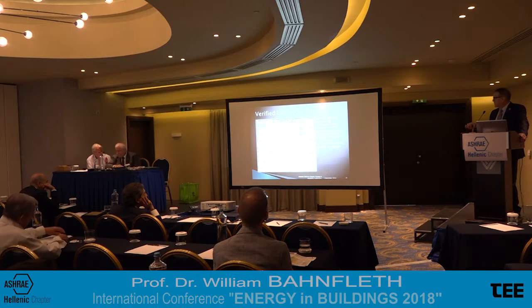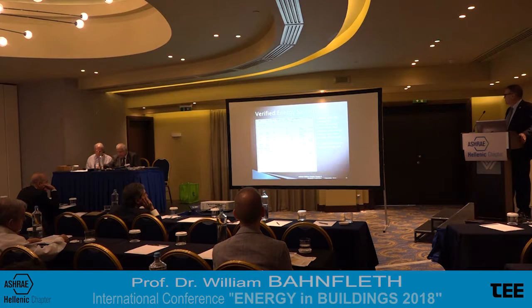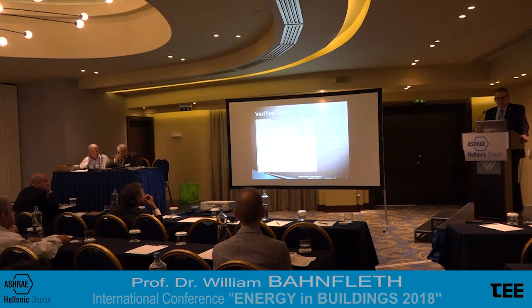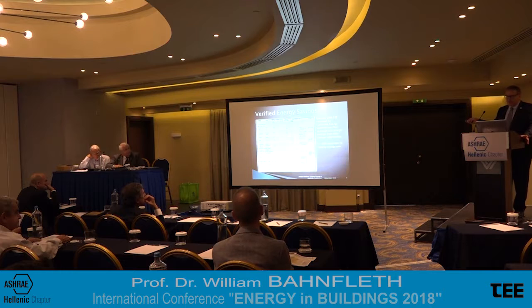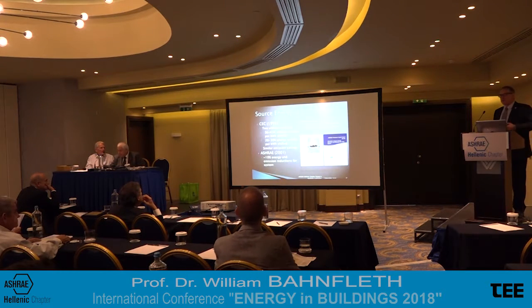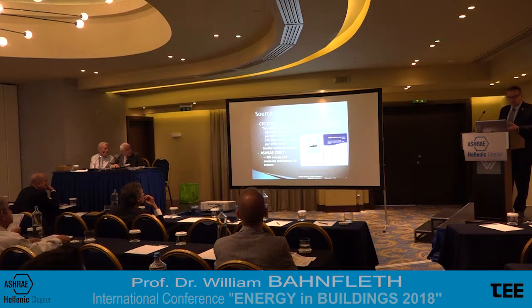retrofit. I don't expect anyone to read this, but it's documented in the link down here, and I imagine the slides can be made available to everyone. What it shows is a number of actual systems in California that were documented to have 3 to 50% reduction in cooling energy after a thermal storage retrofit. So that's the site energy angle, and certainly it's possible, I believe it and have done it myself.